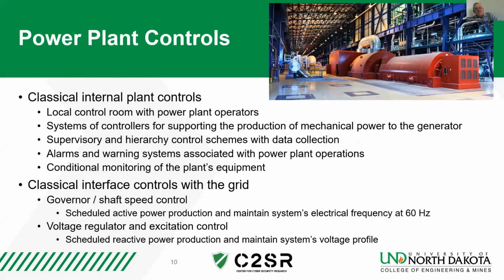Power plant controls. We've talked about that. There's two basically major controls: the internal plant controls for the overall operation of making sure the prime mover is moving, and the classical controls to the control center so that output power can be maintained at given levels. And so part of the classical grid controls is to maintain that the system is operating at frequency, whether 50 or 60 hertz, and make sure that the output voltage is at the prescribed level so that we have proper voltage throughout the grid.